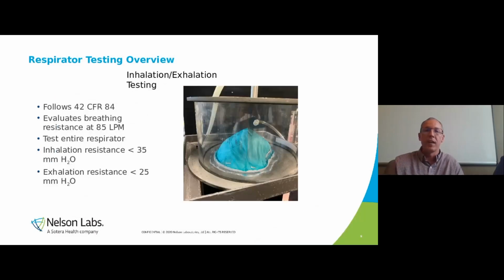So after filtration efficiency, we're going to look at the breathability, called inhalation, exhalation. Again, we test the full device. We mount it to that plate. We pull an 85 liter per minute airflow through. On one side of the mask, we provide the air, and on the other side we have a manometer testing the resistance of the air going through that mask. We test both directions, inhalation and exhalation. On one side we have pressurized air going in, and we measure the resistance. On the other side we pull a vacuum, so we can test both inhalation and exhalation. You'll see the requirements there are less than 35 millimeters of water column for inhalation and less than 25 millimeters of water column for exhalation.